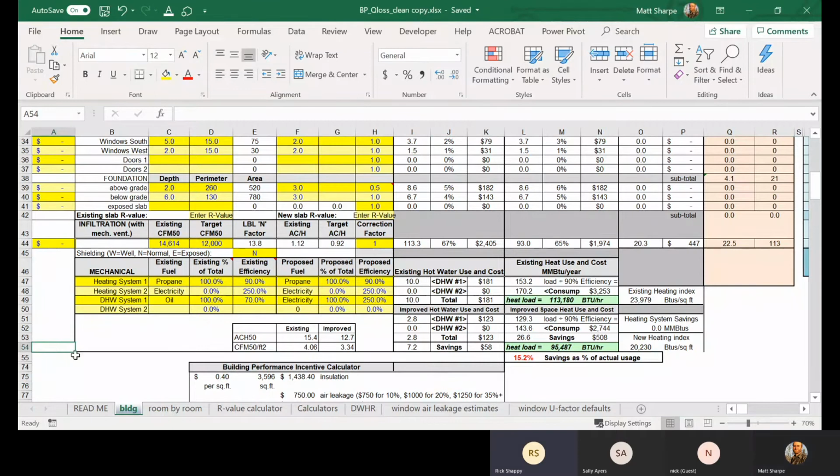So Matt, if you've got doors with a lot of glass, do you enter those in the window section, I'm assuming, or do the doors get subtracted out? Yeah, I'd enter them as the window if it's a glass door in particular, and you might even go so far as entering opaque areas in doors and glazing areas in windows. You could do it either way. If it's a bad door, it's probably not going to be much better than a window anyway, so you could just lump doors with windows. It's not doing any cooling load estimates, so the solar gain is not included at all. It's just R value, U value.